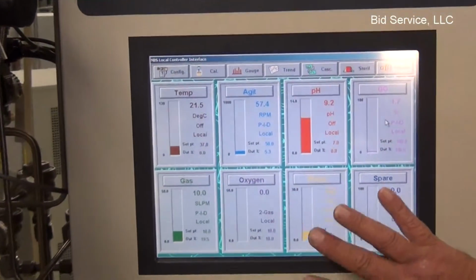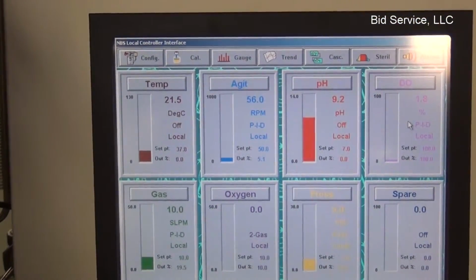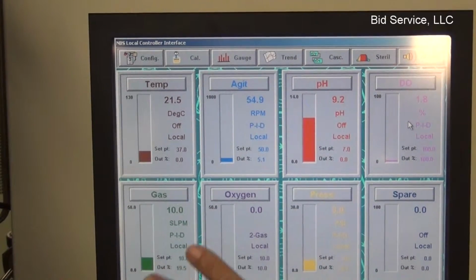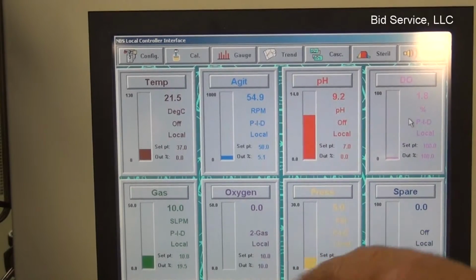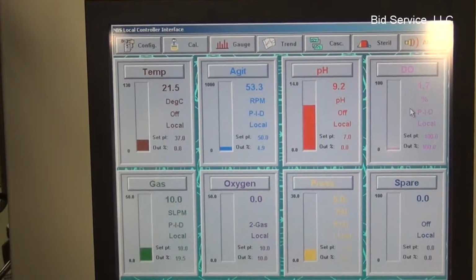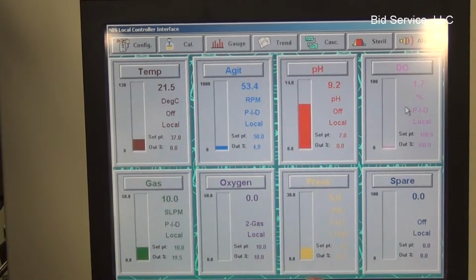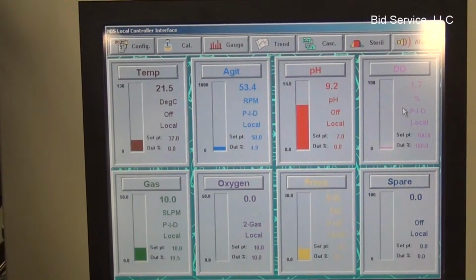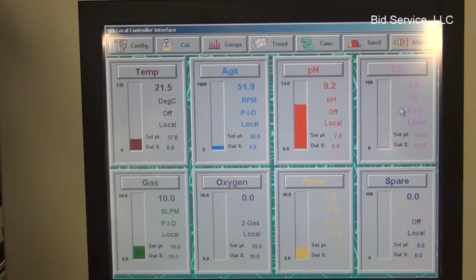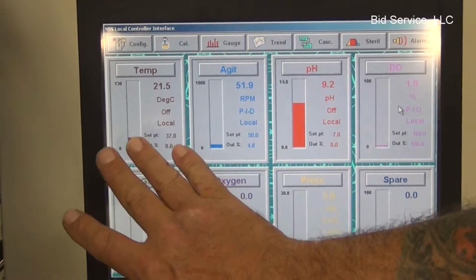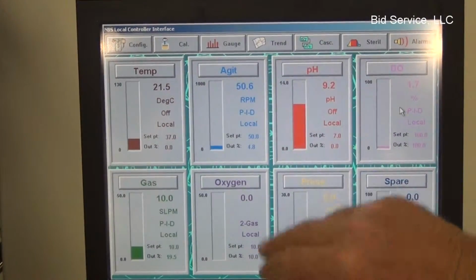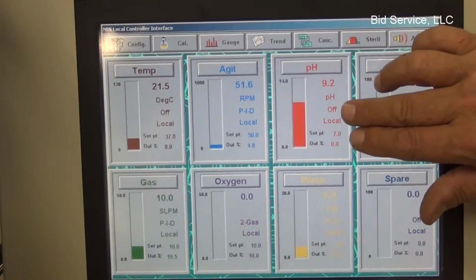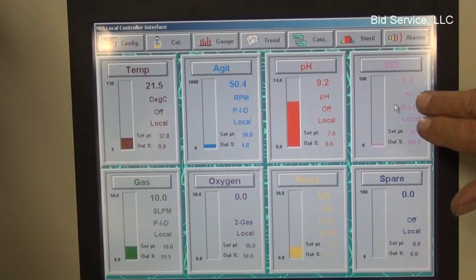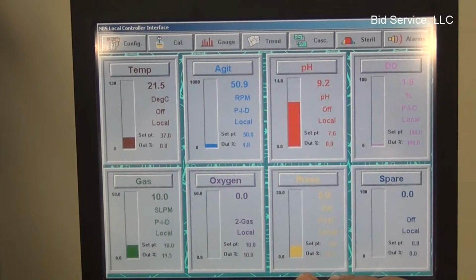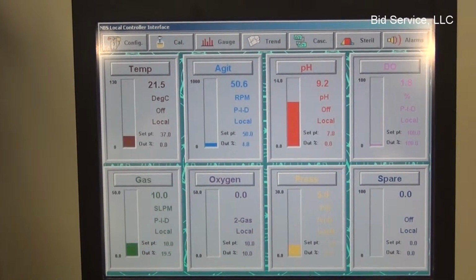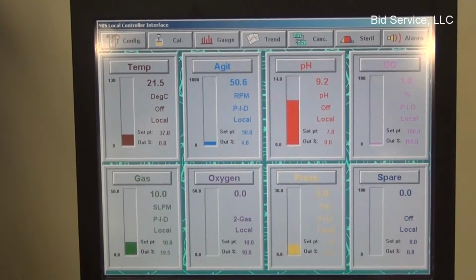Okay. This is the main screen where you'll do all your interactions with the software, configurations, etc. It has different panels for different options. Some of these are here that are not present on this instrument because they are options, but this is the basic configuration that comes with the system when it comes out of the factory. For instance, the temperature is showing here, and it's at room temperature right now. The agitator speed, pH is an option, dissolved oxygen is an option. Pressure here is back pressure through the system. There's a spare in case you needed to hook something external up to it.